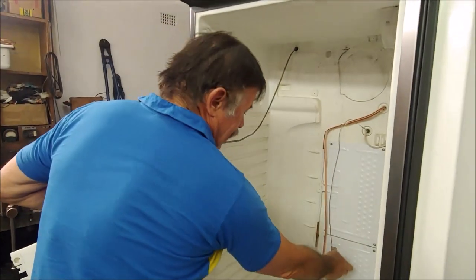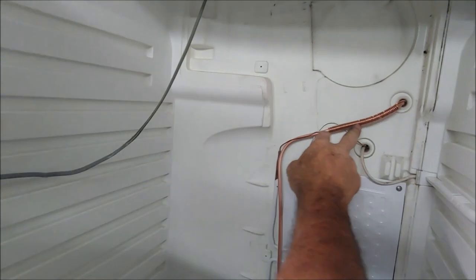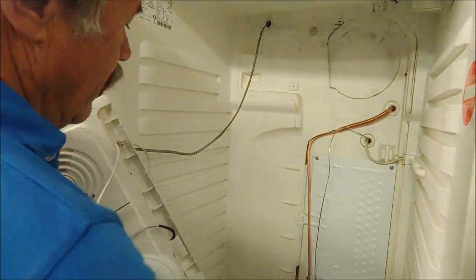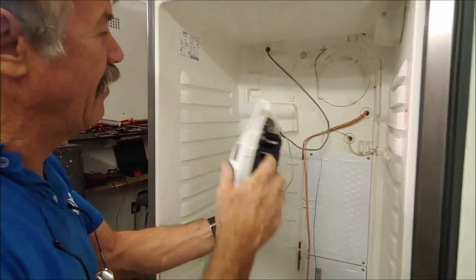I've mounted the two cold plates. This is the suction capillary — I've wrapped the capillary around the suction there just to make it easier to get the right charge. I've mounted the thermostat, Ranco model VT9, and the wire goes out. This is the little low voltage fan motor.